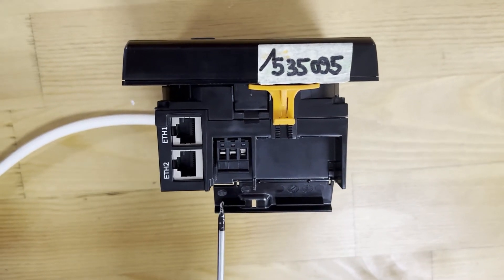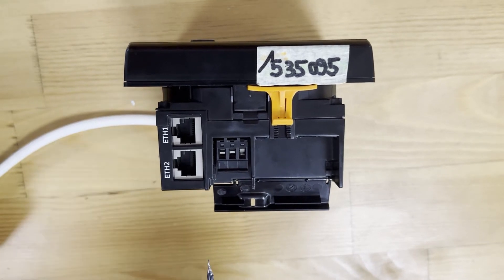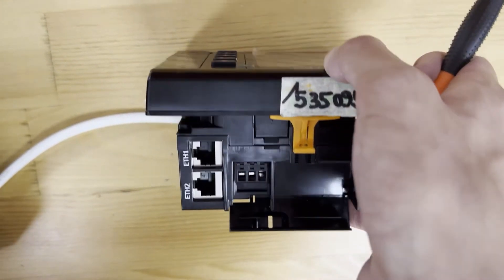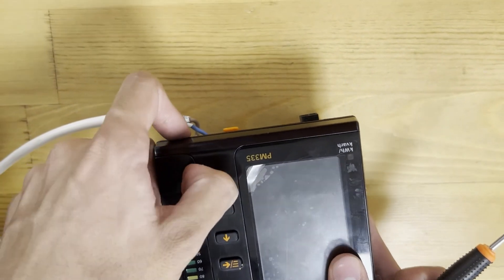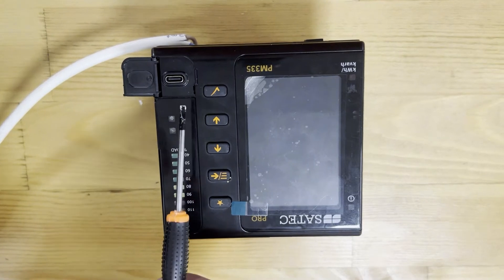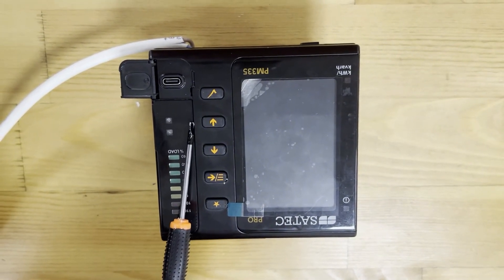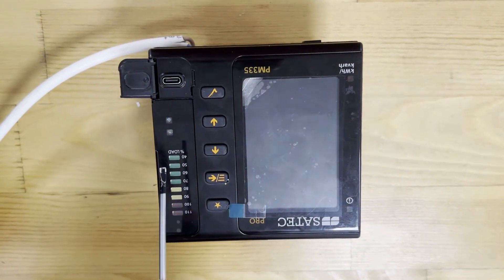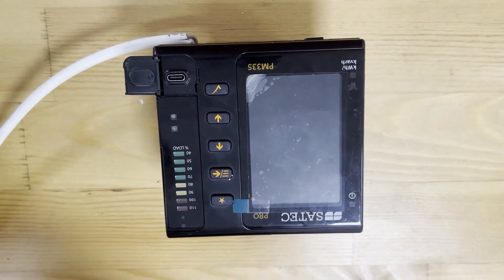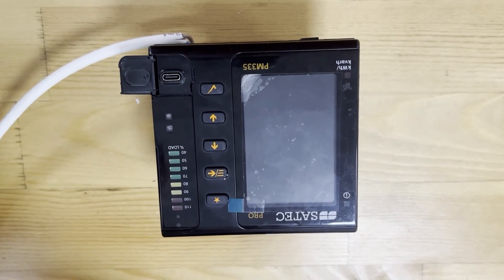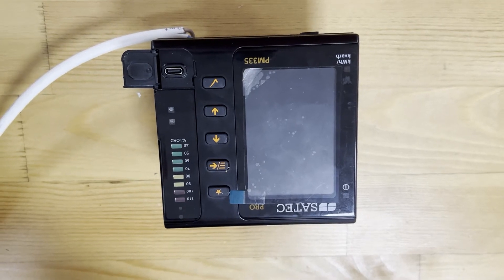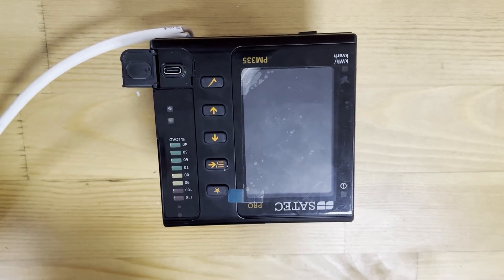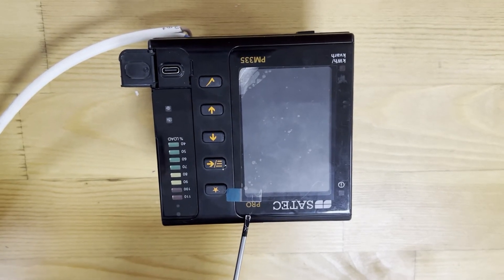The device also has the RS-485 interface, 2 independent Ethernet ports, and an RS port. Here we have the USB Type-C port. A USB node port is for local communication with the supporting PAS software. It's connected directly to the USB port of your PC using the supplied USB cable. No settings are required for USB communication. Simply connect your PC to the pro-meter's USB port and install the supplied USB driver. USB communication is 10 times faster than serial communication at maximum baud rate.